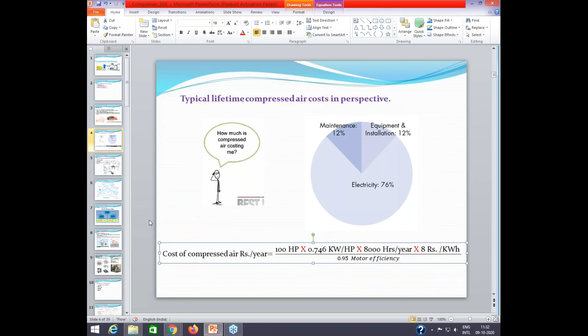Okay, so do this calculation fast, in order to calculate the cost of the compressor in rupees per year. The input is: my compressor is a 100 HP compressor, and it runs for 8,000 hours per year. Assuming it runs up to 8,000 hours per year, the average cost of electricity is 8 rupees per kilowatt hour. And I took the motor efficiency as 95%. Just do the calculation and write your answer in the question box. Suppose your industry has a 100 HP compressor that runs for 8,000 hours per year, and the average cost of electricity is 8 rupees per kilowatt hour. So what is the cost of the compressor per year?